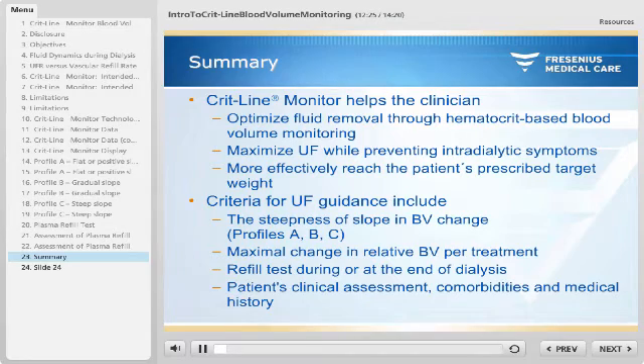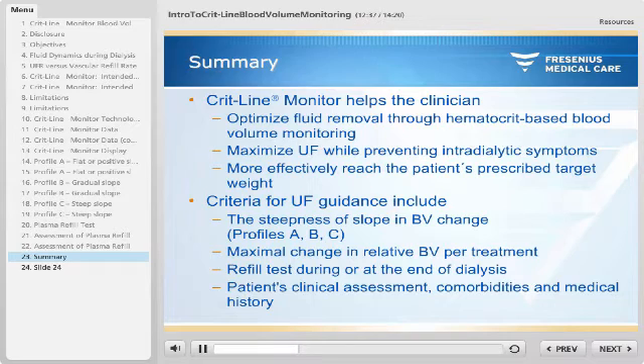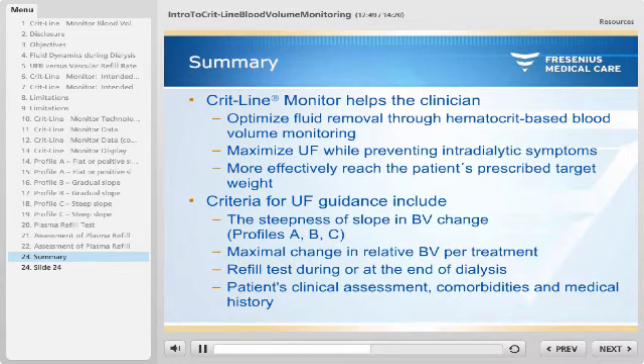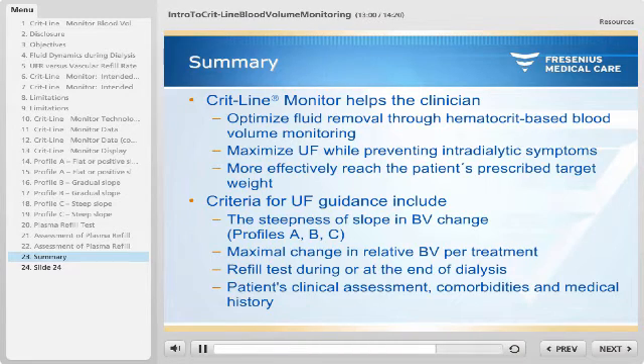In summary, the CRITLINE monitor helps the clinician to optimize fluid removal through hematocrit-based blood volume monitoring, maximize UF while preventing intradialytic symptoms, and more effectively reach the patient's prescribed target weight. Criteria for UF guidance include the steepness of the slope in the blood volume change — that is, profiles A, B, and C — maximal change in relative blood volume per treatment, and refill tests during or at the end of dialysis. Importantly, the dialysis prescription should always consider the patient's clinical assessment, comorbidities, and medical history.